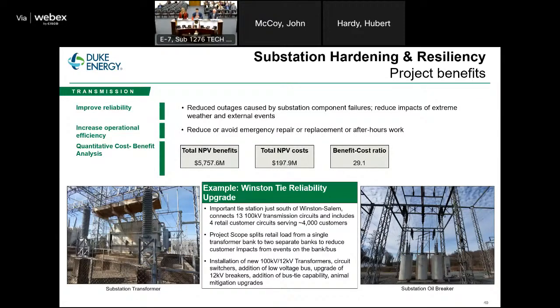The project scope: we are upgrading the transformers to the current standard. We're upgrading the circuit breakers, which I'll talk more about in those specific projects. We're also reconfiguring this station for redundancy. Right now, it's a single transformer bank. So if we do have a fault that occurs on one of the distribution circuits, or if we have a problem within the station on a bus, we basically isolate all of the circuits, right? If the problem is associated with the high voltage bus or the power transformer, we're actually splitting the bank into two separate power transformer banks. This allows us to cross tie load between the two. We can take some circuits out for maintenance if needed, and we have some redundancy built in. So this reliability improvement, again, will benefit the customer served from this station.